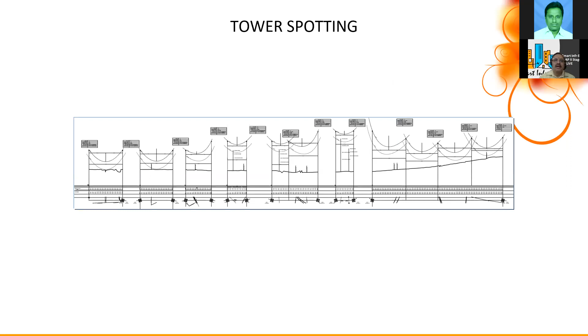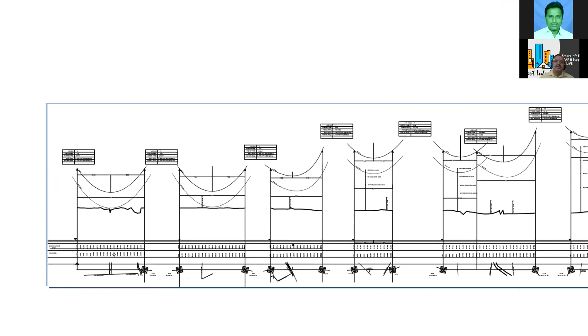Here we give the complete details of each tower: what extension is to be used, the soil type, and the clearance we have. Ground clearance is drawn here, showing the minimum ground clearance. The hot curve is the bottom one and the cold curve is the top one. We consider both when spotting the towers.